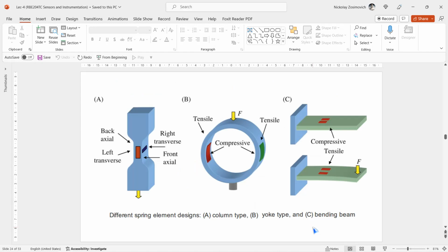You can see four strain gauges on the spring element. The position is chosen such that one pair of gauges is located with compressive stress, and the other pair with tensile stress, or differential mode. If the construction does not allow such a configuration, the two pairs of strain gauges are mounted in a way that one pair expresses the strain that has to be measured, while the other pair is ideally not affected by the strain. The second pair merely serves for offset stability and temperature compensation. And obviously, the construction of the spring element and the strain gauge arrangement determines the major properties of the device.